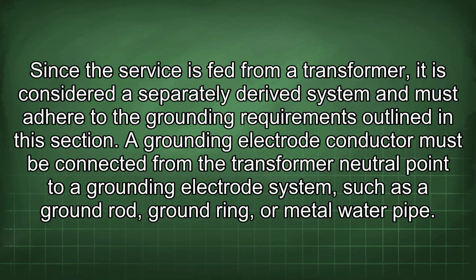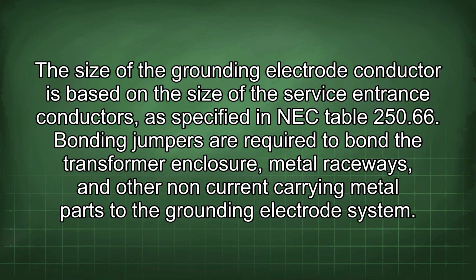Since the service is fed from a transformer, it is considered a separately derived system and must adhere to the grounding requirements outlined in this section. A grounding electrode conductor must be connected from the transformer neutral point to a grounding electrode system, such as a ground rod, ground ring, or metal water pipe.